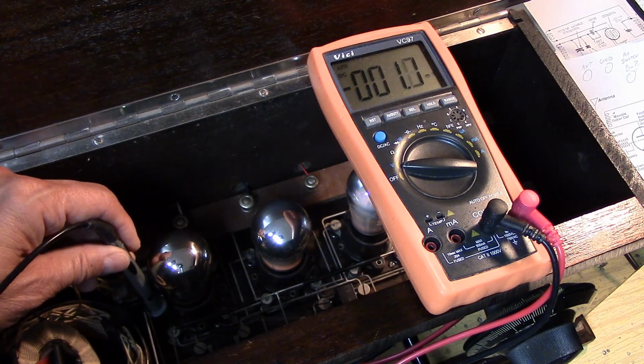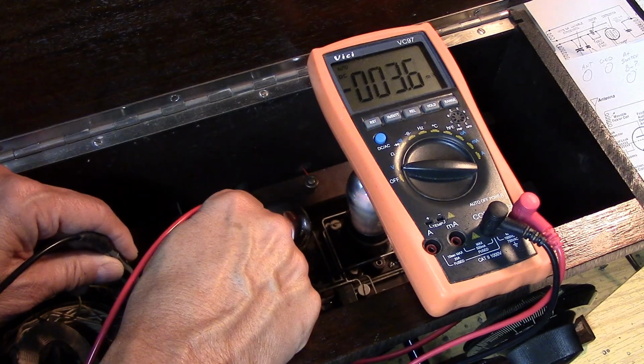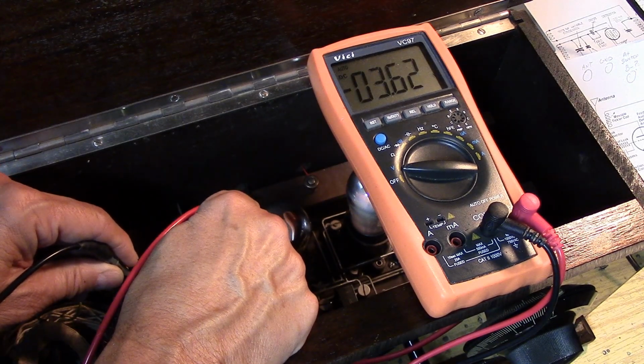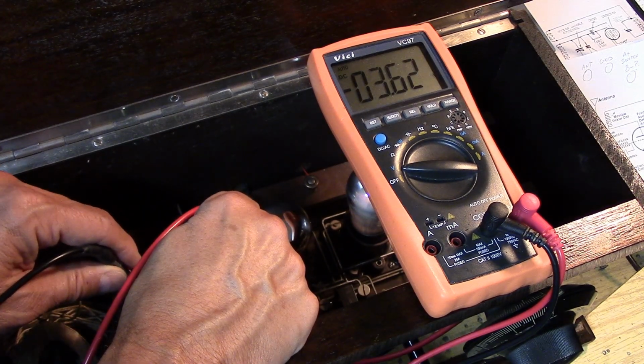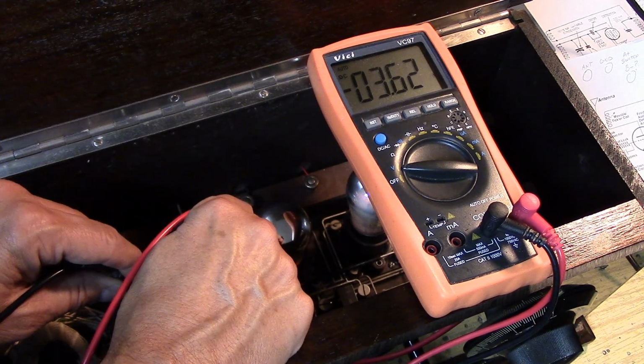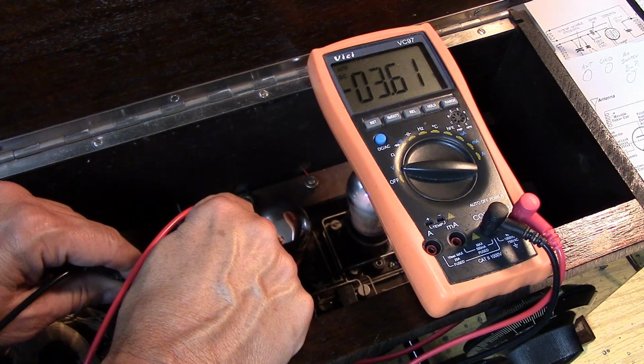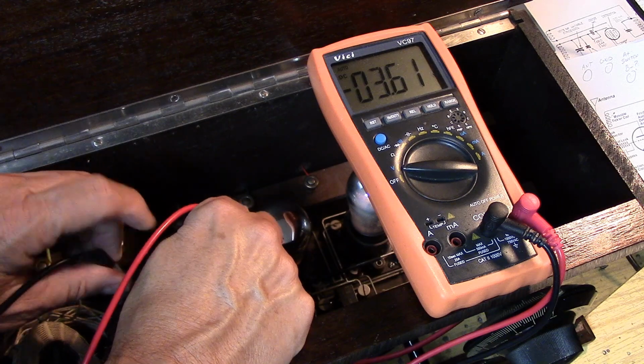So let's look at the filament, see what we got across it. Only 3.6 volts. So we need to adjust the detector's filament voltage as well, and that's done with a separate rheostat.